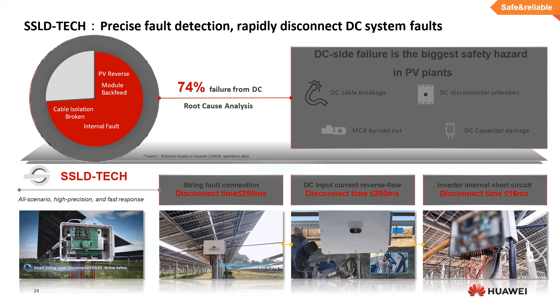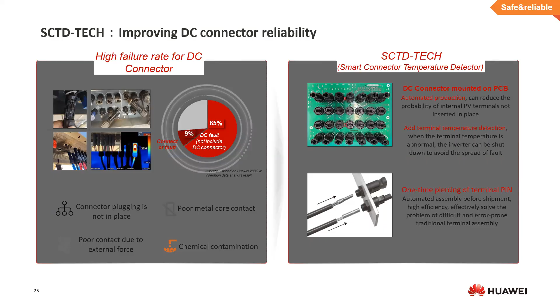The connector quality is improved in the new Huawei inverters. This is the picture on the right side. You can see that the connectors are mounted on a PCB sheet with an automated procedure. This is done to reduce the probability of an internal PV terminal not being inserted in place, due to which the temperature of this connector can be raised. So whenever the temperature of any connector is abnormal, the inverter will be shut down.